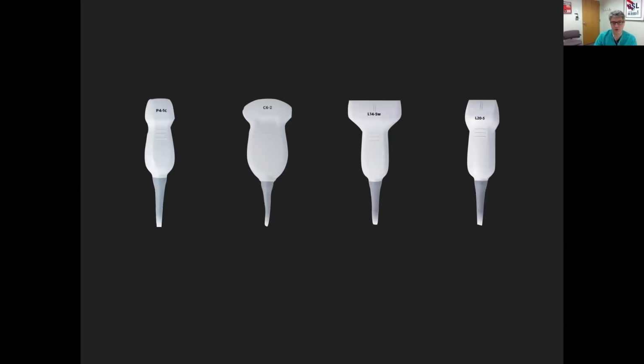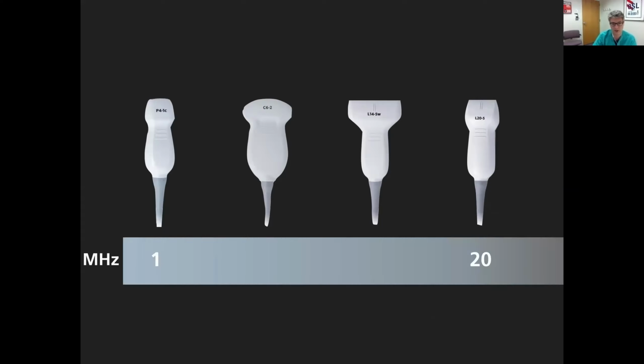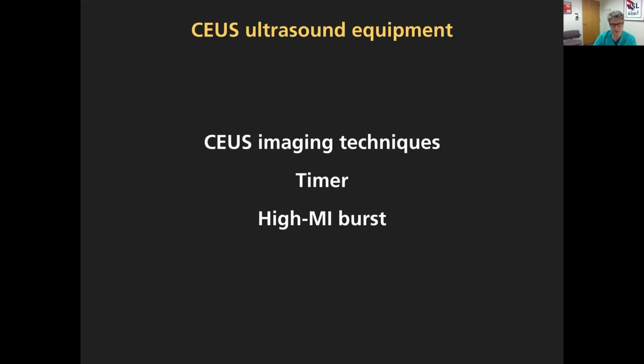So what about transducers? These are the transducers that we have. You can see a wide range from 1 to 20 megahertz. We're obviously not going to scan at 20 megahertz with the contrast package, but you have a very wide range of transducers for all kinds of applications for contrast enhanced imaging. The equipment usually has these imaging techniques. They typically have a timer, because if you're looking for any injury pattern or solid organ injury, you want to know, are you in the arterial phase? Are you in the venous phase? And then typically they have a button for the high MI burst, so that's easy to do.